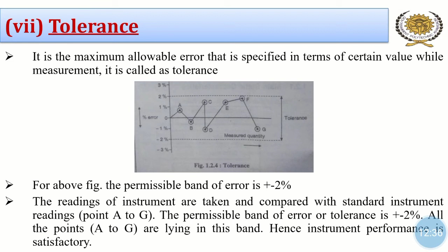Next, tolerance. It is the maximum allowable error that is specified in terms of a certain value while measuring. It is called tolerance. For the above figure, the permissible band of error is plus or minus 2%. The readings of the instrument are taken and compared with standard instrument readings. The image shows points A to G. The permissible band of error or tolerance is plus or minus 2%. All the points A to G are lying in this band. Hence, instrument performance is satisfactory.